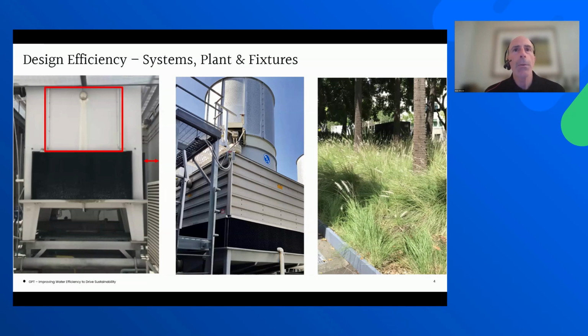Also design issues for fire service systems. It's really good at the outset to ensure you've got sufficient isolation valves to reduce the losses that take place when the sprinkler systems are periodically drained down.